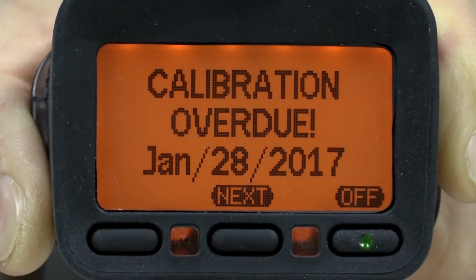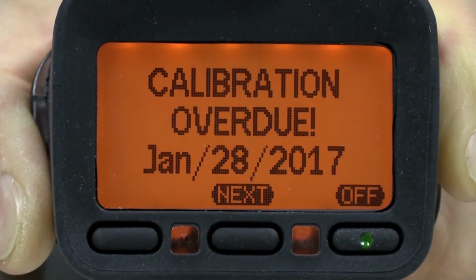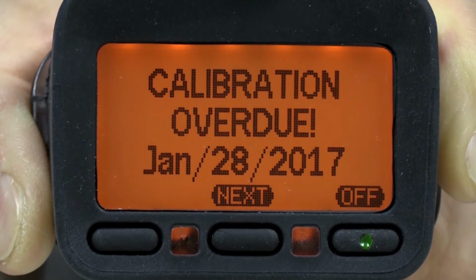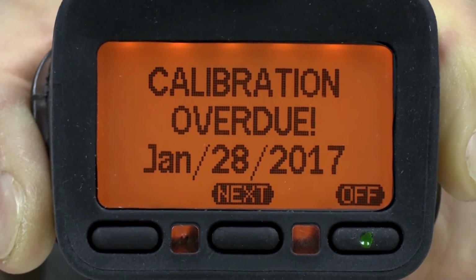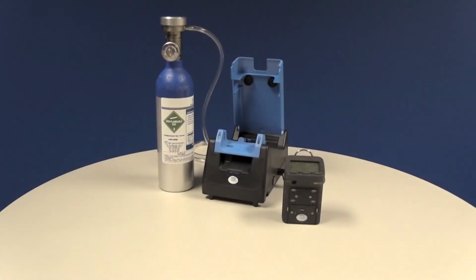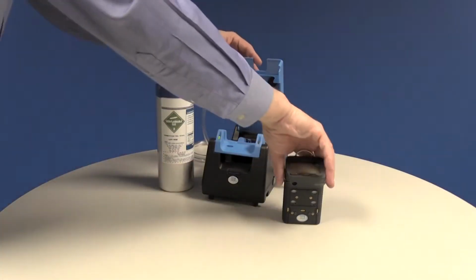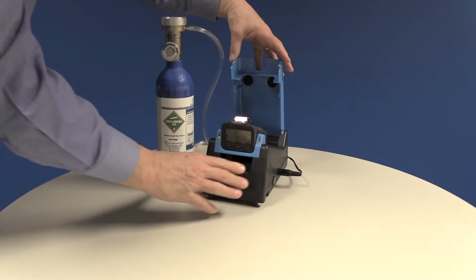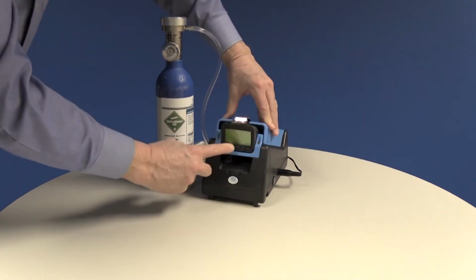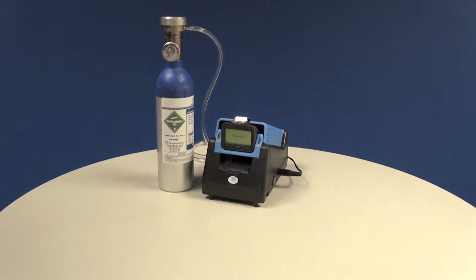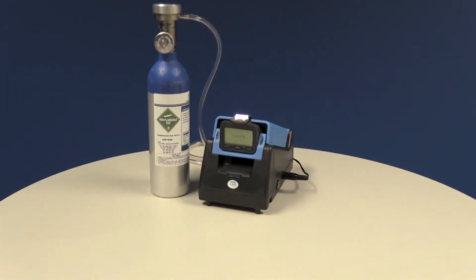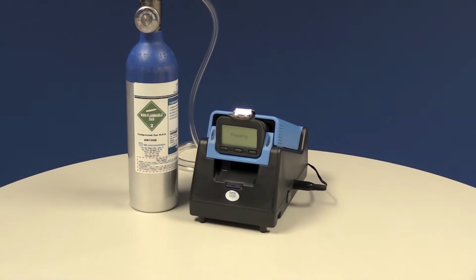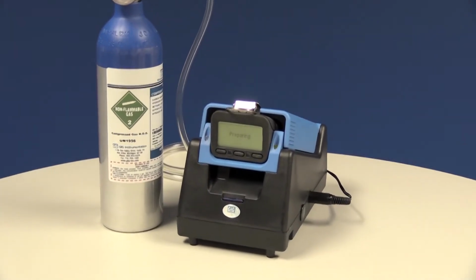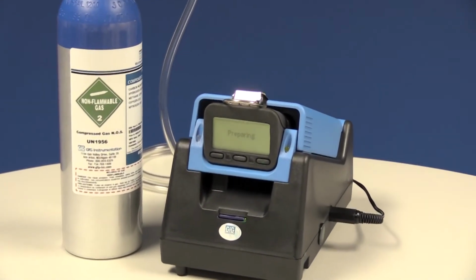The calibration overdue alarm is cleared by performing a full calibration. The calibration can be performed manually or by means of a DS400 automatic test and calibration station. To use the docking station, all you need to do, once again, is insert the instrument into the cradle. You can press the button to start the calibration procedure immediately or wait for the countdown to be completed and for the procedure to be started automatically.